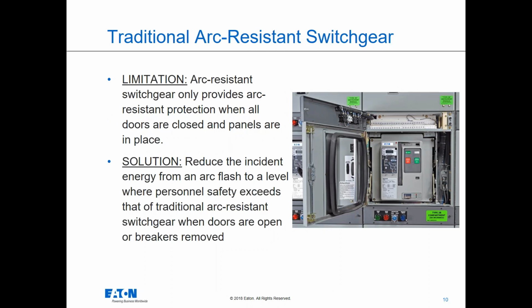When you open a type 2B metering compartment or control compartment, you're safed off. Those compartments are labeled and able to be accessed while the equipment is live without having to carry or wear the PPE required to protect you from an arc flash around that equipment. But let's say you have to fully rack out and withdraw a breaker. That may be due to needing to replace a trip unit, add a shunt trip, add an aux switch, or move a key interlock. There may be many reasons why that breaker needs to be removed.